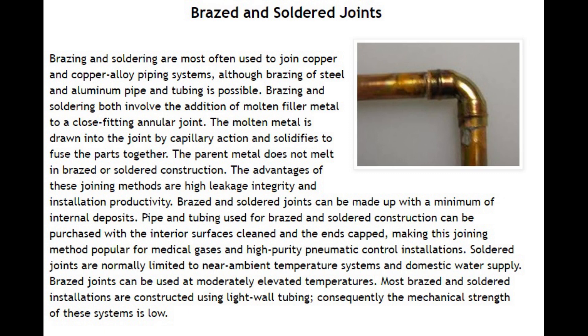Brazing and soldering are most often used to join copper and copper alloy piping systems, although brazing of steel and aluminum pipe and tubing is possible. Both involve the addition of molten filler metal to a close fitting annular joint. The molten metal is drawn into the joint by capillary action and solidifies to fuse the parts together. The parent metal does not melt in brazed or soldered construction. The advantages of these joining methods are high leakage integrity and installation productivity. Brazed and soldered joints can be made up with a minimum of internal deposits.